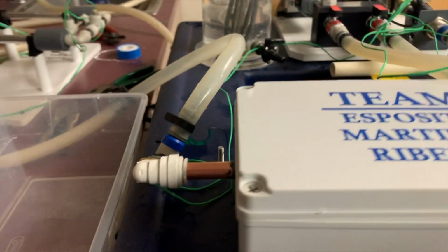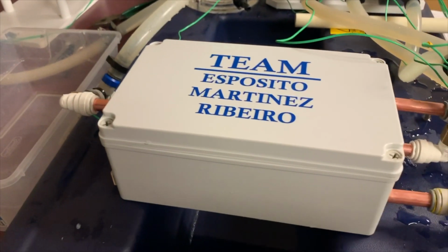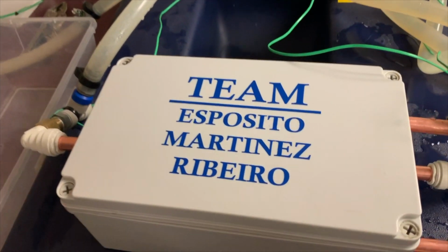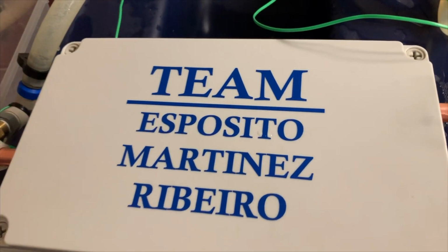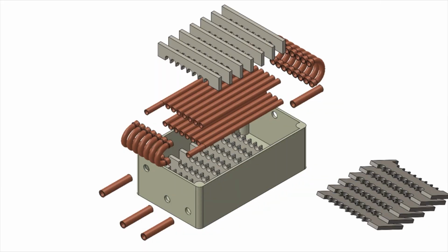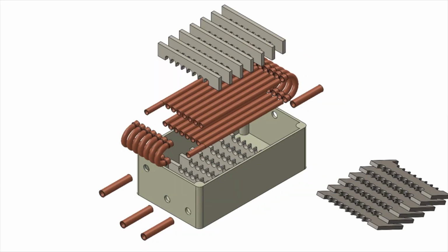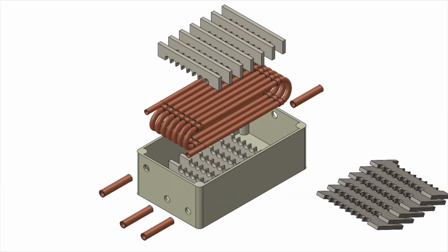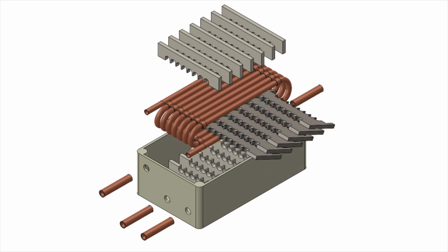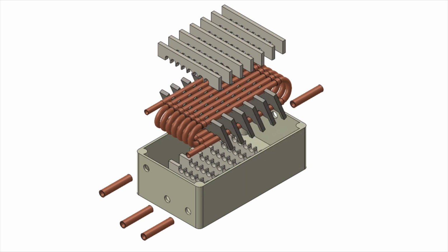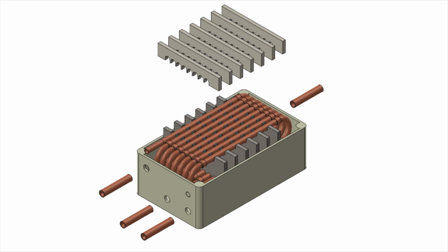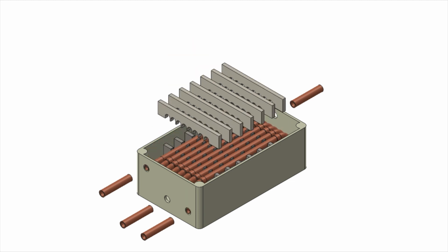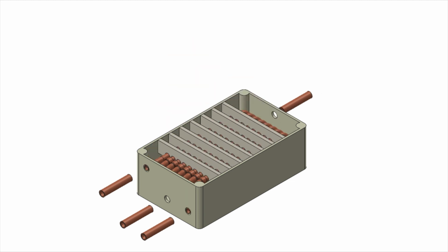The heat exchanger tubes had 30 thousandths of an inch thick walls and a total pipe length of approximately 12 feet 3 inches to maximize the contact area while keeping the thermal resistance low and staying within budgetary constraints. The hot water transfers heat rapidly via conduction through the thin copper tube walls, and then heat transfer is dominated by turbulent forced convection to the cold water flowing through the enclosure. Turbulence is generated and maintained by a network of acrylic baffles.